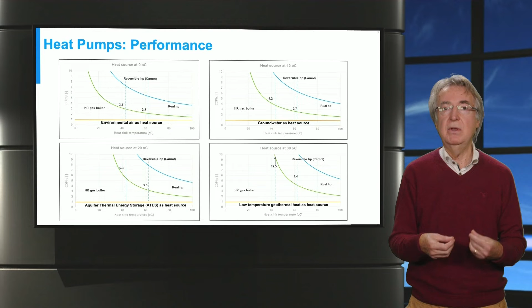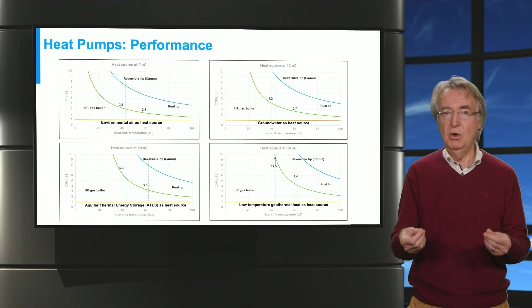Similarly, for aquifers or ATES at 20 degrees Celsius, and geothermal heat at 30 degrees Celsius as heat source, the COP of the heat pump for 40 degrees Celsius sink temperature will be 6.3 and 12.5 respectively. So we see that the COP of the heat pump depends largely on the heat source and sink temperatures. If we can use aquifers and geothermal heat sources, then we can have high COPs for heat pumps. Let us look at heat pumps available in the market.